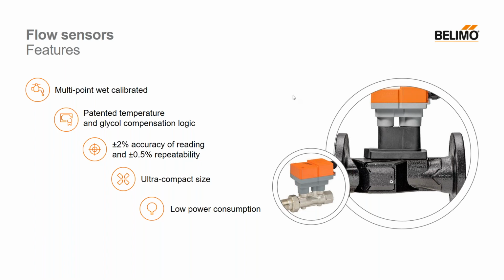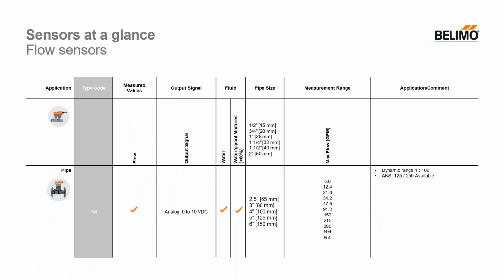So at the time, this is not an insertion style meter. It's a simple volumetric ultrasonic flow meter that uses transit time technology. Very accurate, very cost effective, and in new installations, it's a great product. It's a great product if you've got the pipe open and you can fit either a threaded or a flanged flow metering product in there. The reliability and point of purchase cost make this a really competitive and high quality product to install.